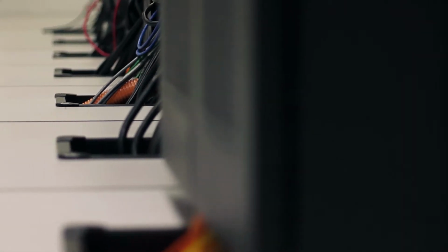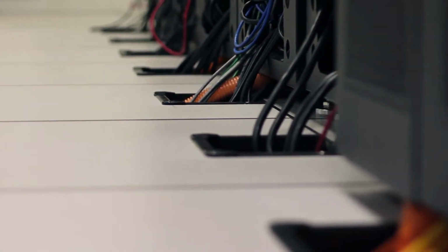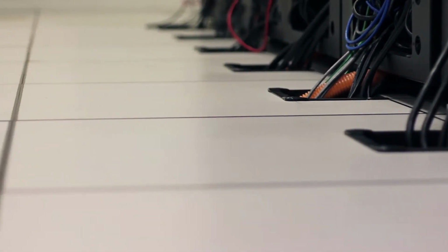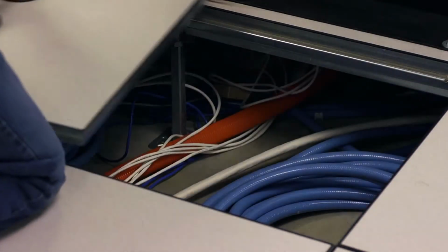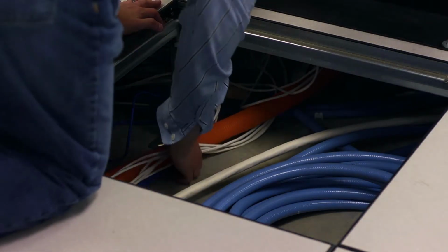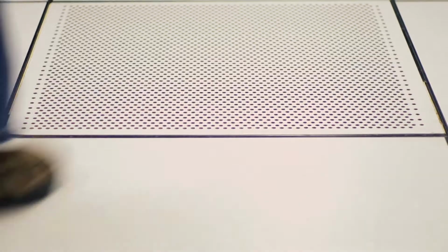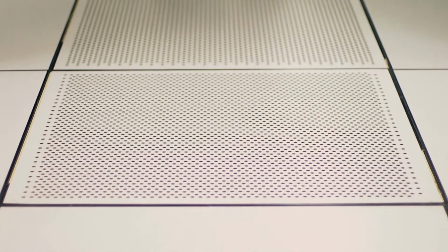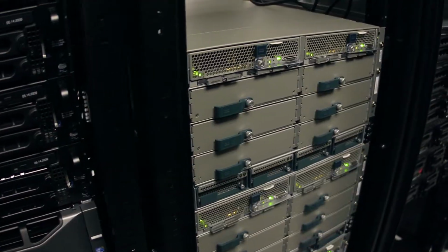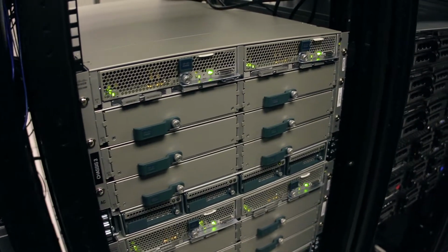You'll notice the entire space is raised flooring. The point is twofold: first, we do cable management under there for networking and power. Also, it's the management system for environmental controls. Down the middle of the aisle, all the tiles have holes in them, bringing cold air up from the floor into the front of the servers.